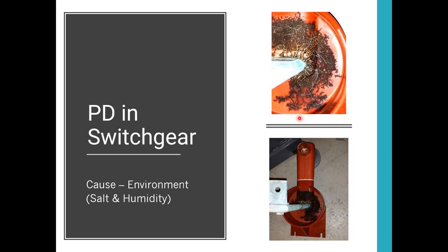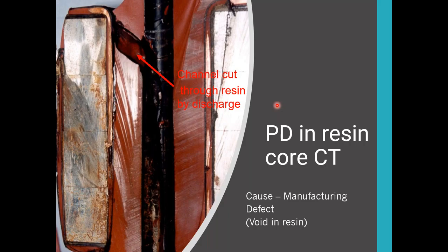They go through, and they regularly find this. And this is an almost annual replacement where they replace these. It's normal maintenance for them. They use the handheld instruments to identify them, and they just go in and replace it. If this was back on the mainland, in a substation here, this would cause people to freak out because you shouldn't see this level of PD build up in short periods of time, but it's the environment they're in. There's nothing they can do about it. So they just have a warehouse of replacement parts and they just regularly go through and replace them.